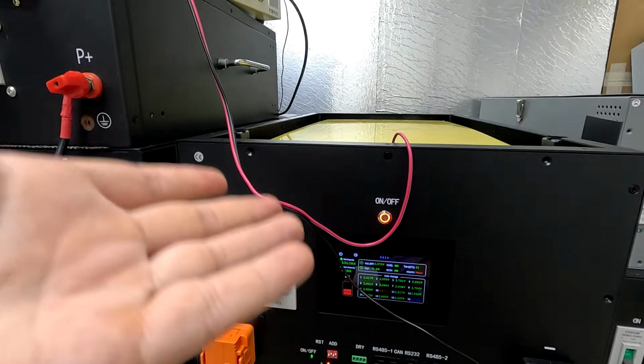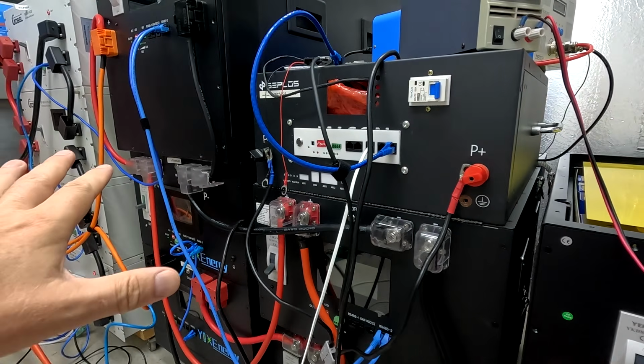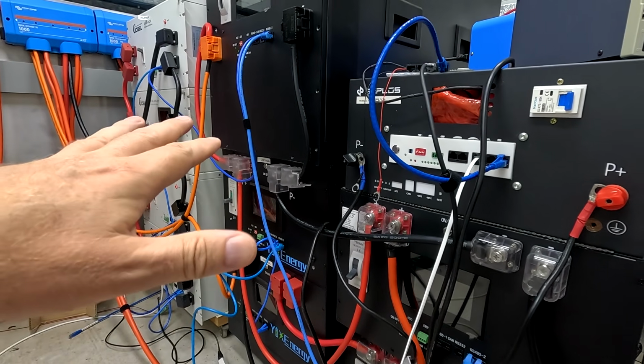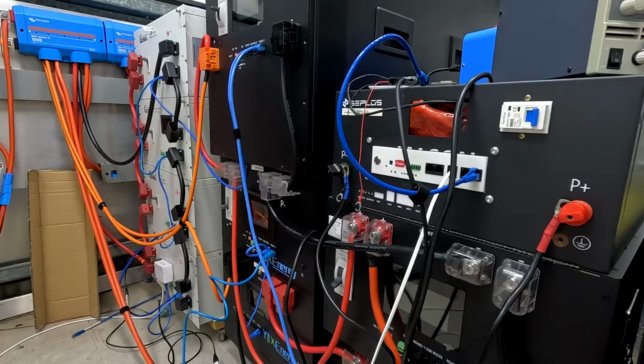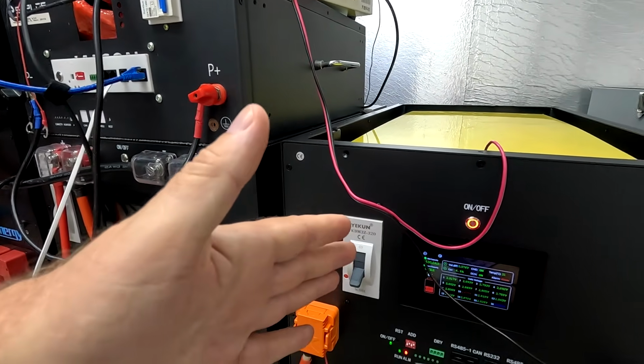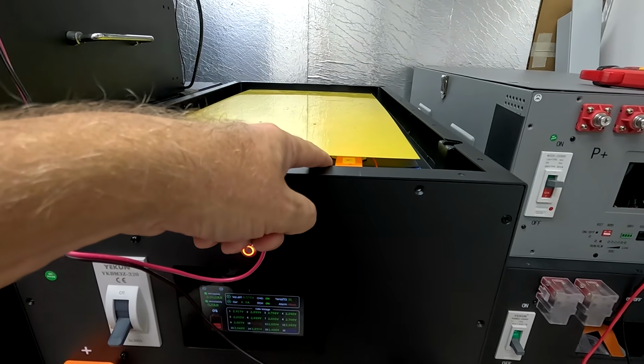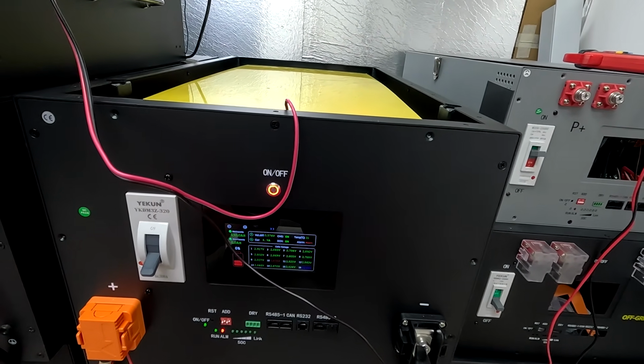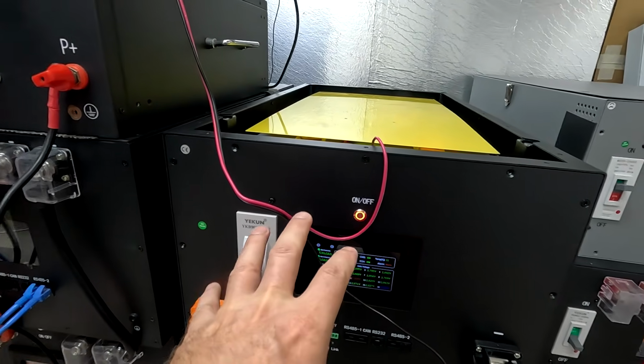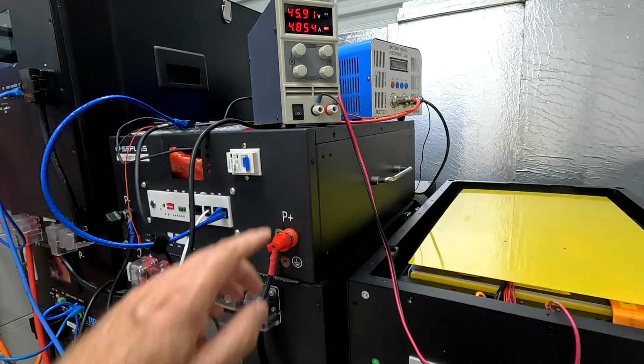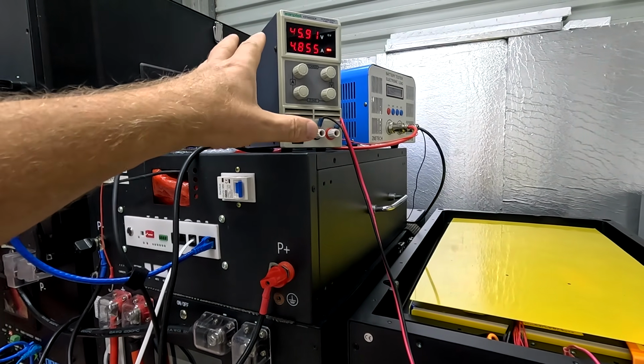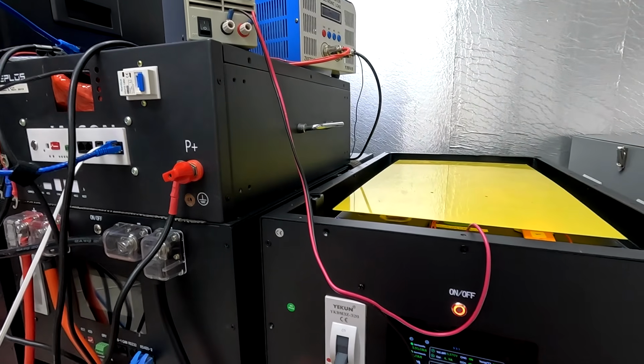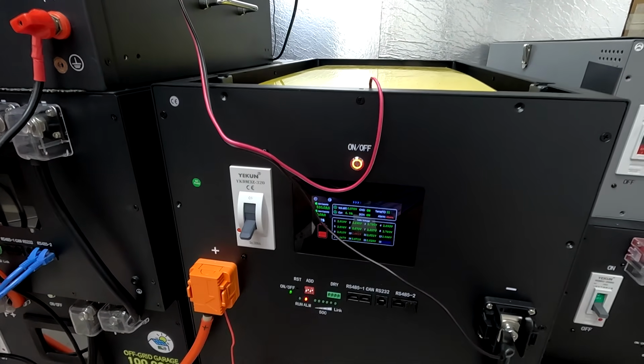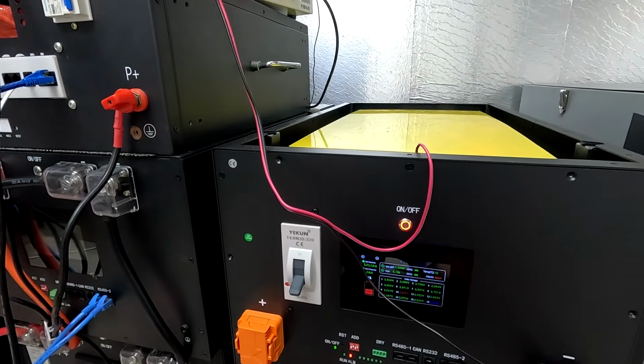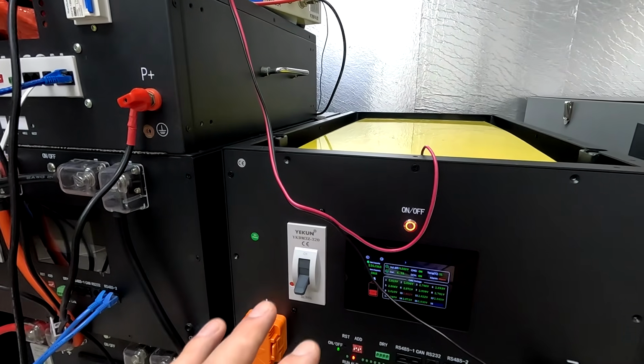But we have to lift the voltage up again before we can turn on this breaker, because all the other batteries I have connected again now are at 53.9, 54 volts. This would be a huge inrush current into this battery and could potentially kill the 300 amp fuse inside, trip the circuit breaker and the BMS as well. Something you definitely cannot do - connect an empty battery to a stack of full batteries. So we have to wait until this voltage comes up to 52 volts or so, maybe 51.5, and then we can turn on the circuit breaker again. If it still gets an overcurrent, the current limiter will kick in and limit the current to 10 amps. But I would never do this in this state now - there would be a couple hundred amps going into this battery then. Not good.